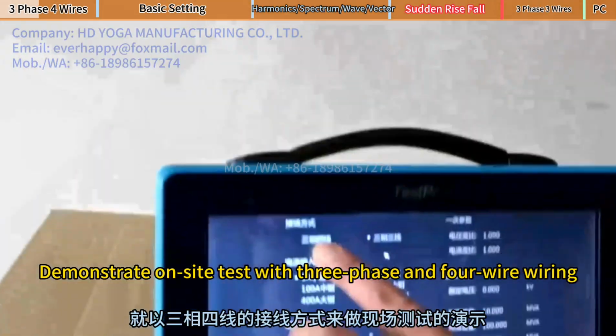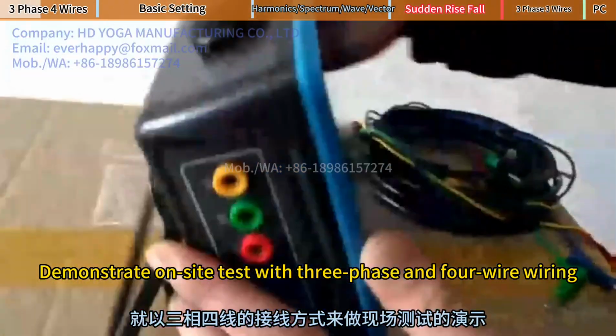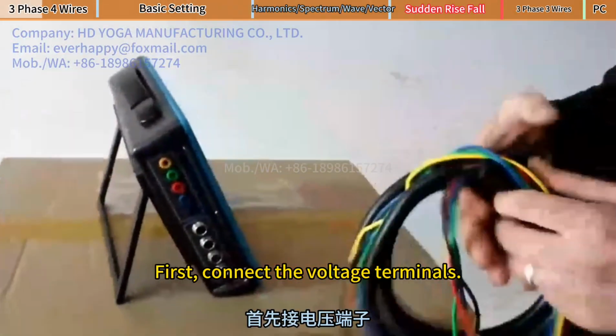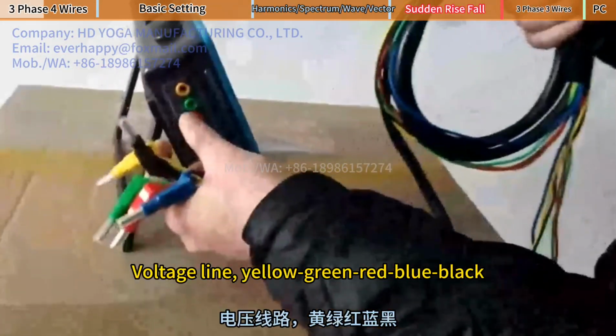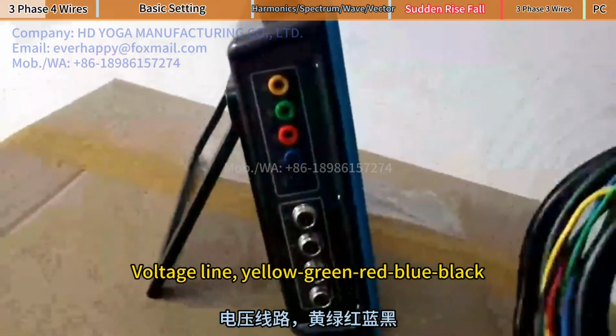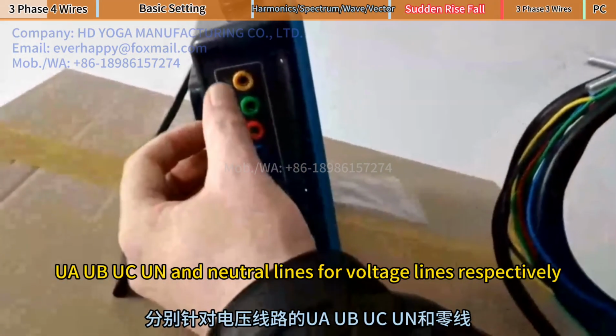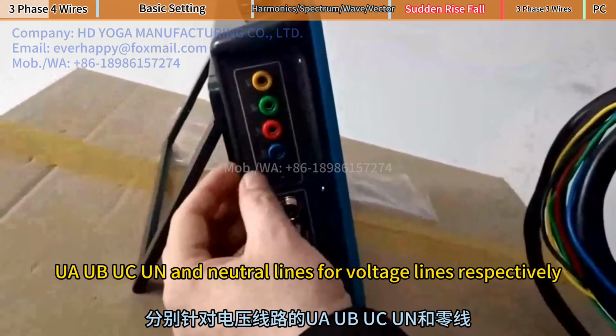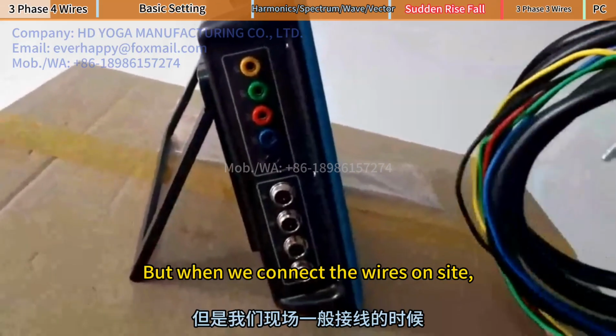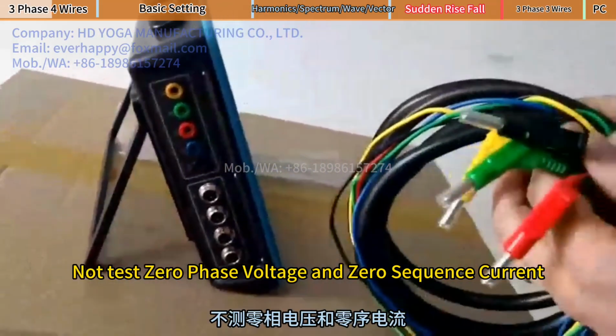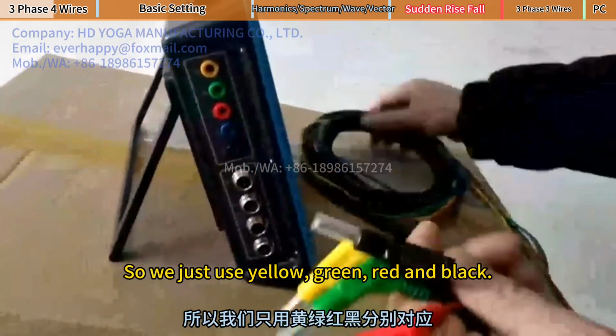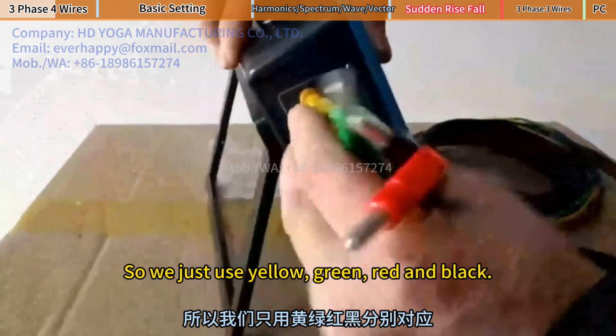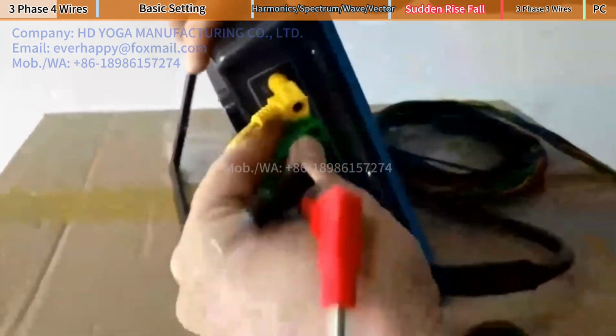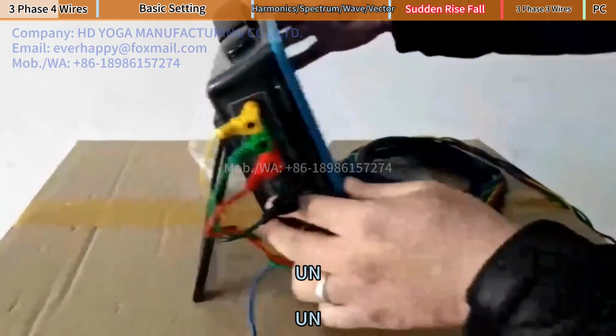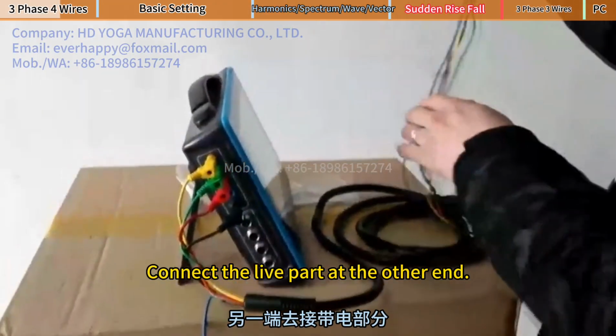Demonstrate on-site test with 3-phase 4-wire wiring. First, connect the voltage terminals. Voltage lines: yellow, green, red, blue, black. UA, UB, UC and neutral lines for voltage lines respectively. But when we connect the wires on site, we do not test zero-sequence voltage and zero-sequence current, so we just use yellow, green, red and black: UA, UB, UC, UN.